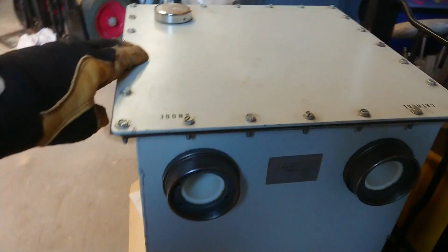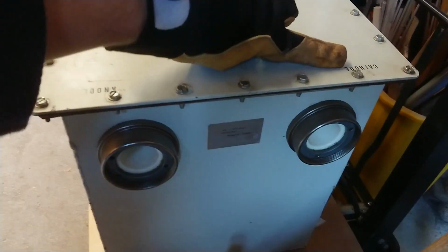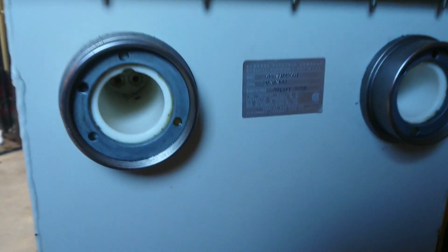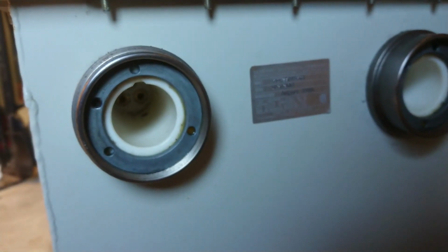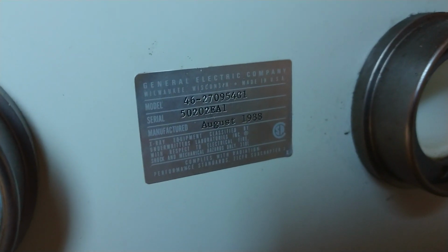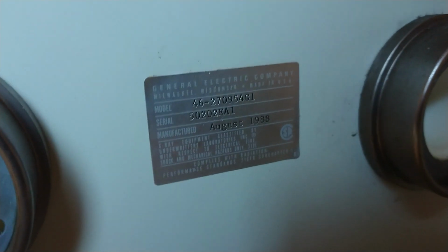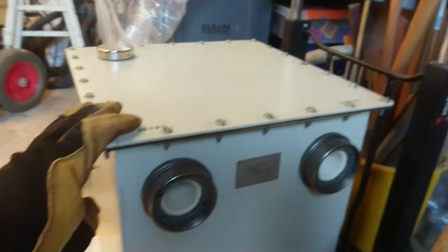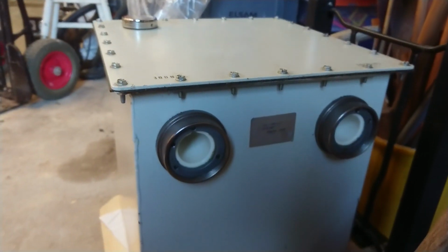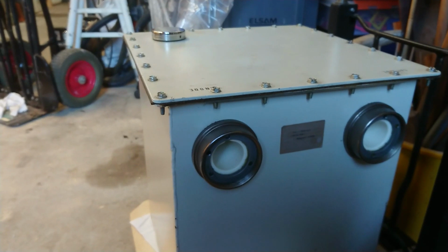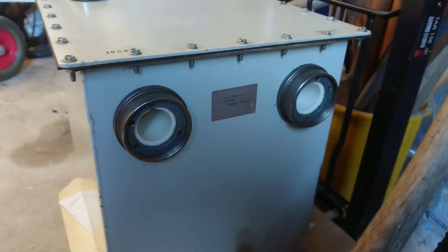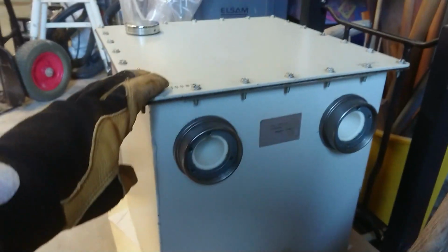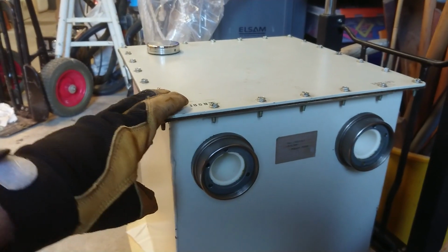So now if we look at the other side of the transformer, we can see over here the anode and cathode connections. And this is a standard shockproof connector. It's quite deep and has 3 small brass sockets. And if we can see the date here, it's August 1988. So the transformer here is roughly 9 years younger than the control panel itself. I will not take this apart, as this is full of transformer oil, so that's quite a mess.